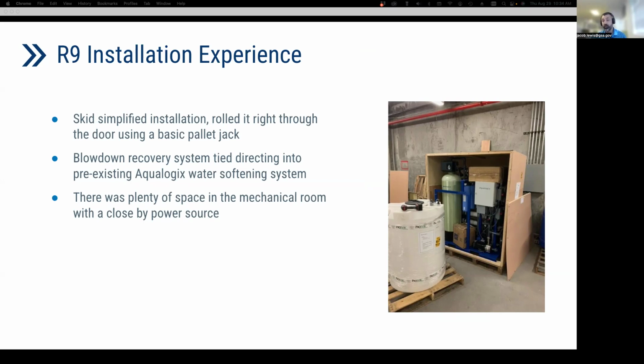The actual installation for both systems was fairly easy. The physical installation for both was done over a weekend. With the water softening system, we had to do some hot taps and tie directly into the water systems in the chiller room, and it plugged directly into a wall outlet. Both systems were small enough to wheel right into the room using pallet jacks. For the blowdown recovery system, the manufacturer came out and did all the pipe connections. The only thing we had to worry about was running power to the system, which we had from an adjacent electrical closet. So all in all, the installations were done over a weekend, and then the company had to come in and do some fine tuning, and they were on site for approximately a week for each installation.